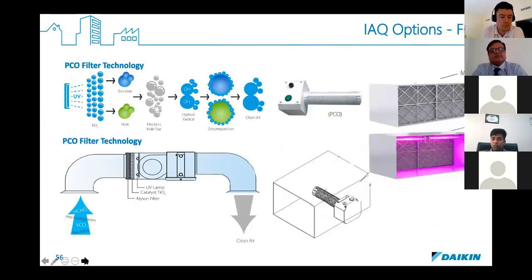Next one, please. And in terms of fan coil units, what can be done? Yes, definitely you can change the filter, but you cannot go to absolute high efficiency because of the fixed fan and the ESP that is available. And you don't want the noise either, because it's very close to the usage. So the filtration available, yes, a plain UV light upgrade is possible.